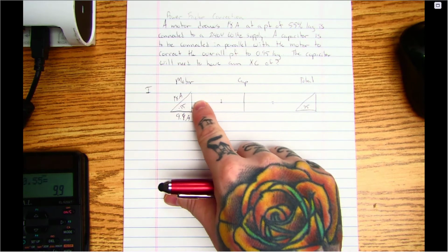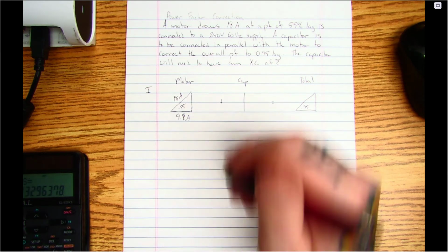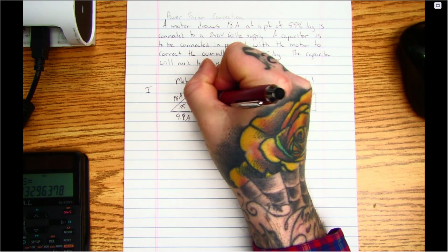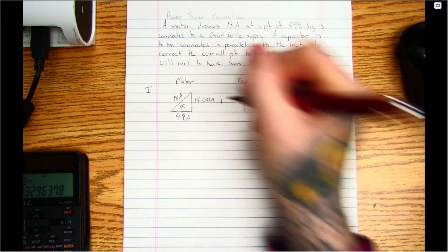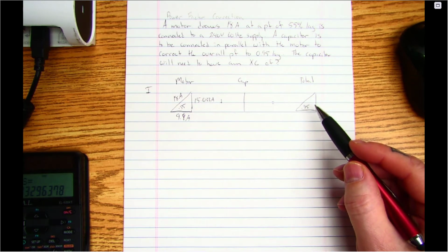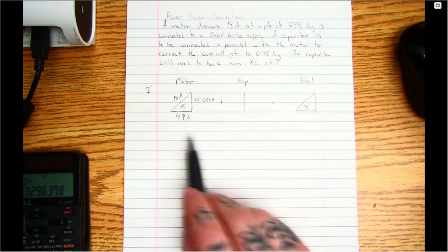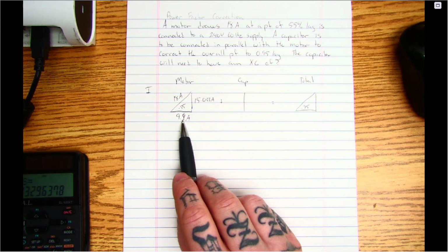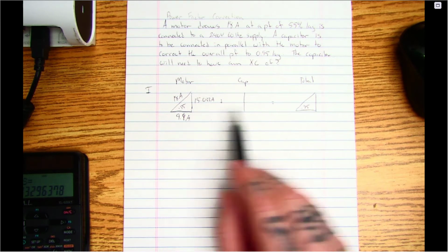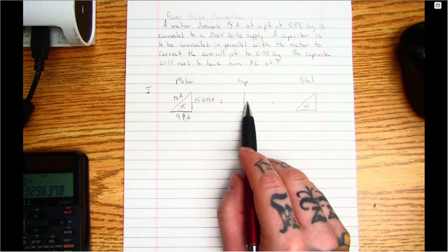When I want the reactive portion of current, I just go 18 squared minus 9.9 squared, and then take the root, and I get 15.033 amps here. So now in these types of questions where they've given you a power factor to correct it to, the only thing we can bring over to this triangle is the resistive portion of current, or the in-phase portion of current. Because we're going to be changing the reactive portion of current by adding a capacitor in parallel.